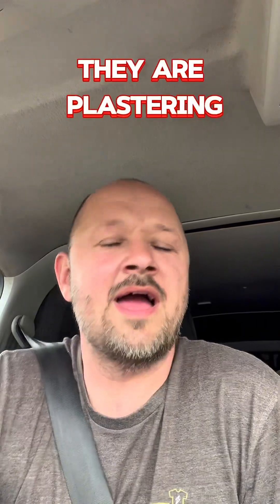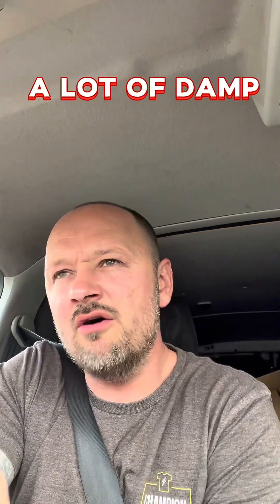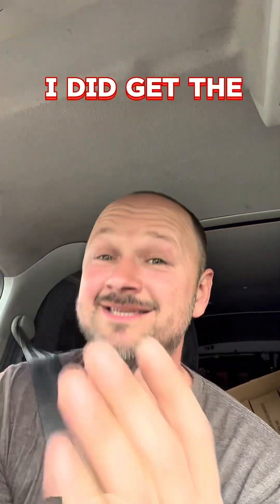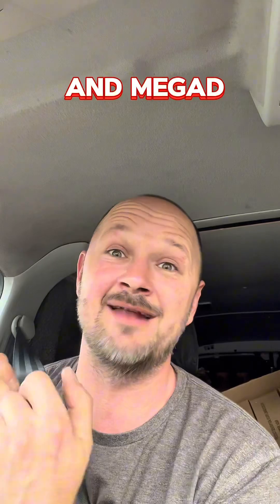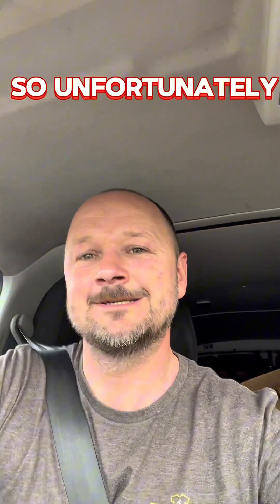But they were still getting a shock. Why? They're plastering in the room with the light hanging down. There's not a lot of damp in there, but you can get an earth through the plaster on the wall, which is fine. I got the tester out and did a continuity test and a megger test between the live and the pipework and between the neutral and the pipework, and got nothing.